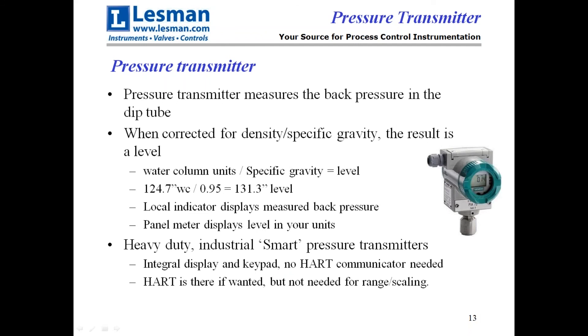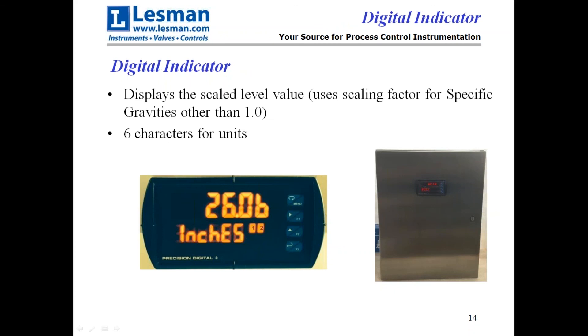We use a pressure transmitter to read the back pressure in the tube to give us the level reading. These are industrial-rated smart pressure transmitters — they have HART. You don't have to have HART to set them up; we configure both the transmitter and display to read level directly per your specification. Most people will take the signal back to a control system to get an electronic reading and do their control off it.